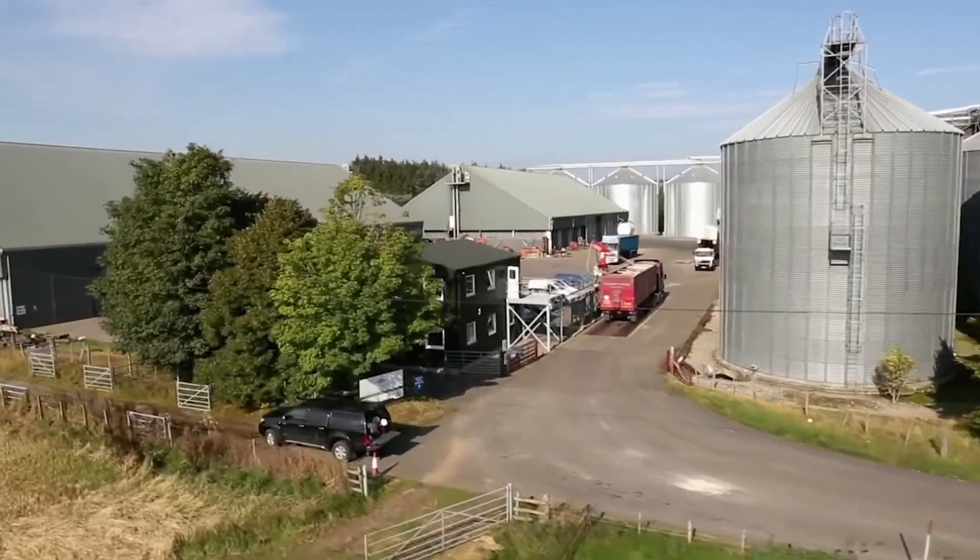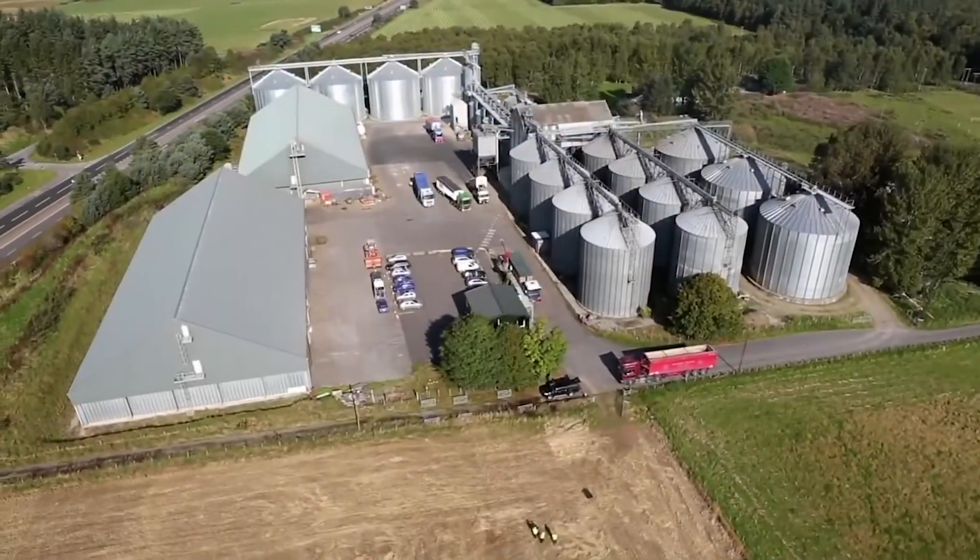And how is it that you are using the Agrolux system? The Agrolux system is installed in 15 of our silos — that's all of our dry silos that we have malting barley in. It monitors the grain for us very, very closely during both our drying season and also on long-term storage. We are looking for different things at different points, particularly during our drying season when we need to very closely monitor the malting barley which is coming off the dryer at much higher temperatures. We need to make sure it's not too high and take action on that accordingly.